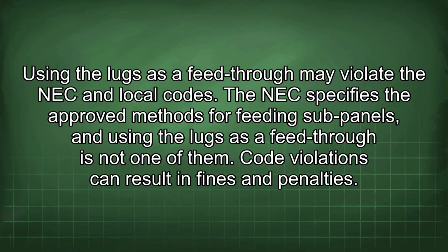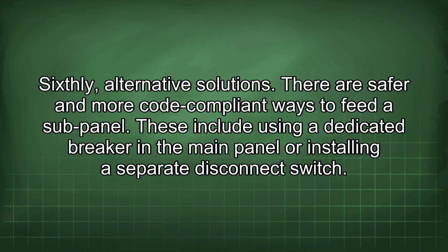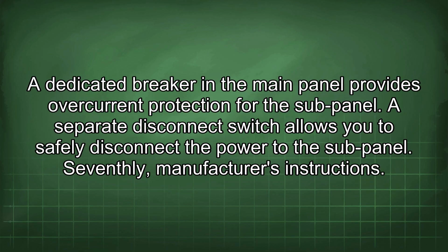The NEC specifies the approved methods for feeding sub-panels, and using the lugs as a feed-through is not one of them. Code violations can result in fines and penalties. Sixthly, alternative solutions. There are safer and more code-compliant ways to feed a sub-panel. These include using a dedicated breaker in the main panel or installing a separate disconnect switch. A dedicated breaker in the main panel provides overcurrent protection for the sub-panel. A separate disconnect switch allows you to safely disconnect the power to the sub-panel.